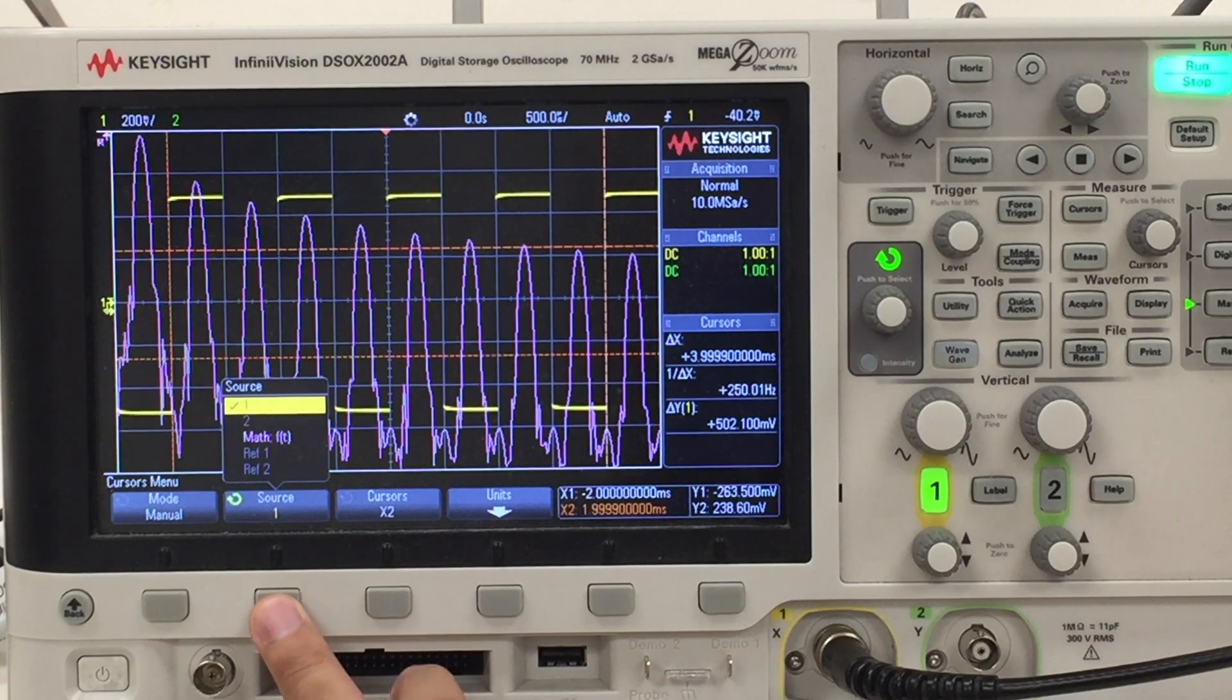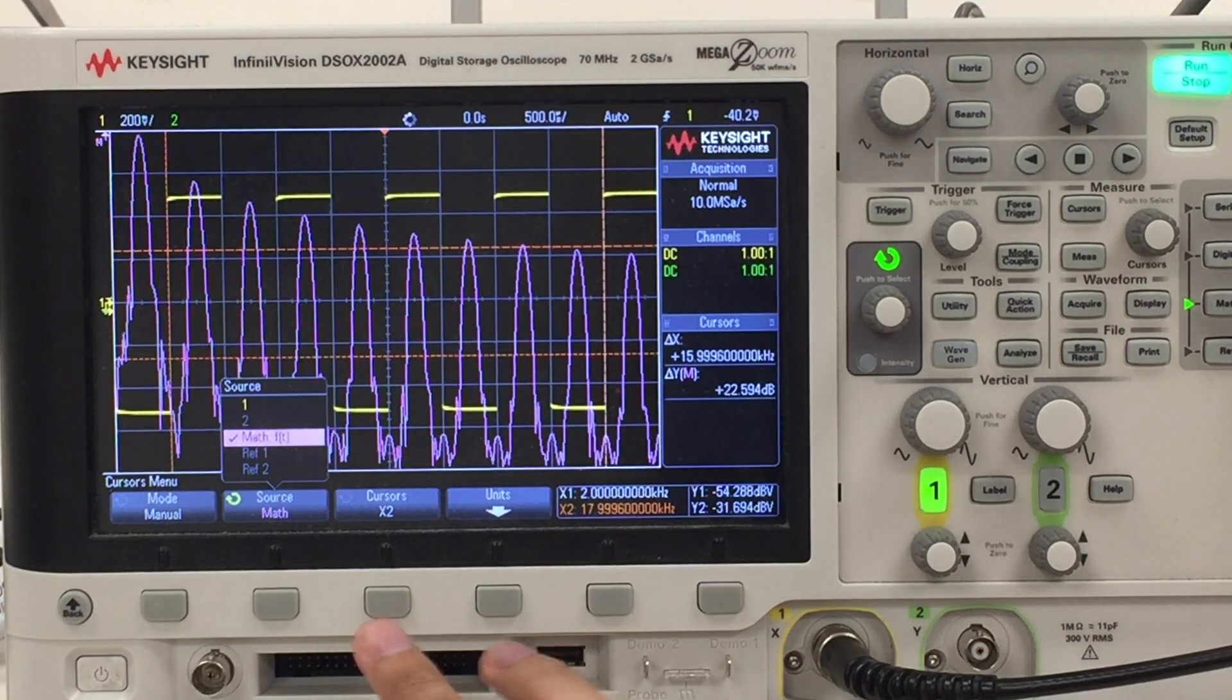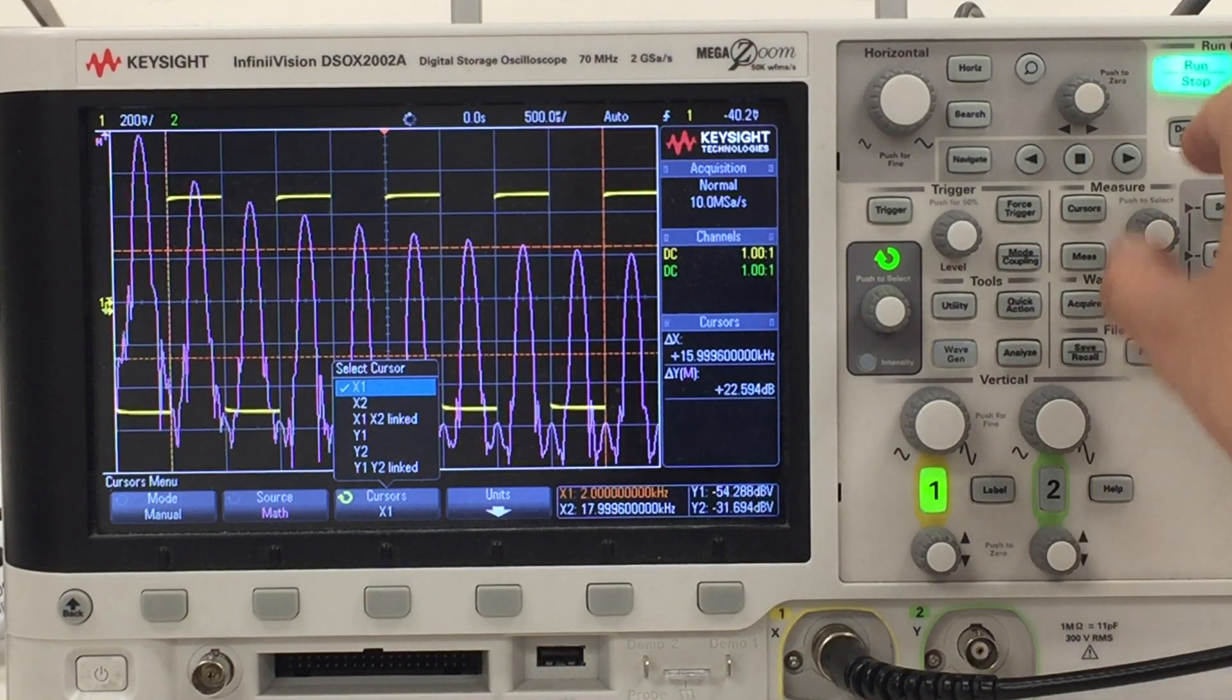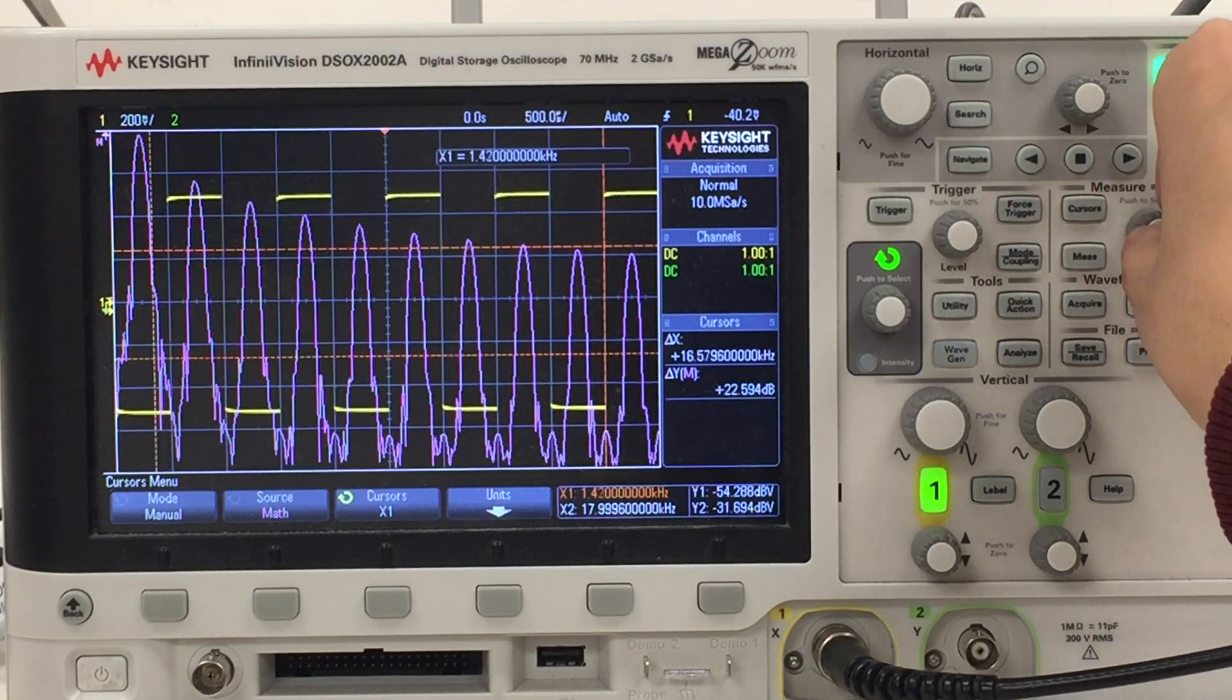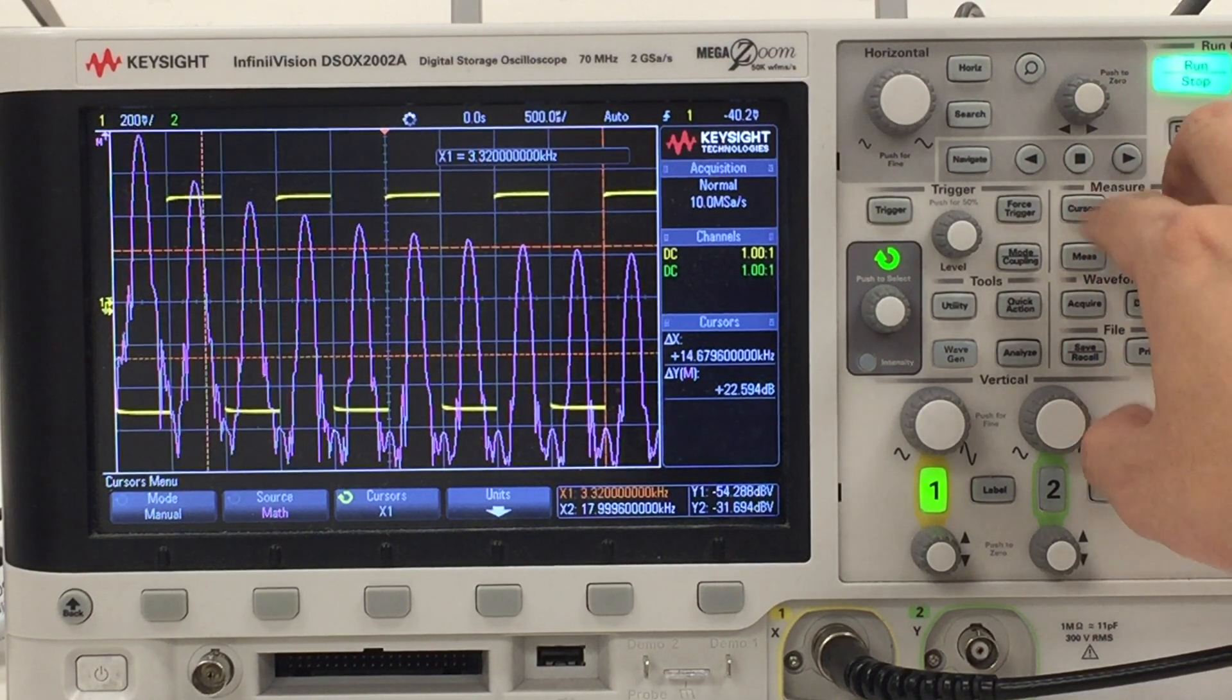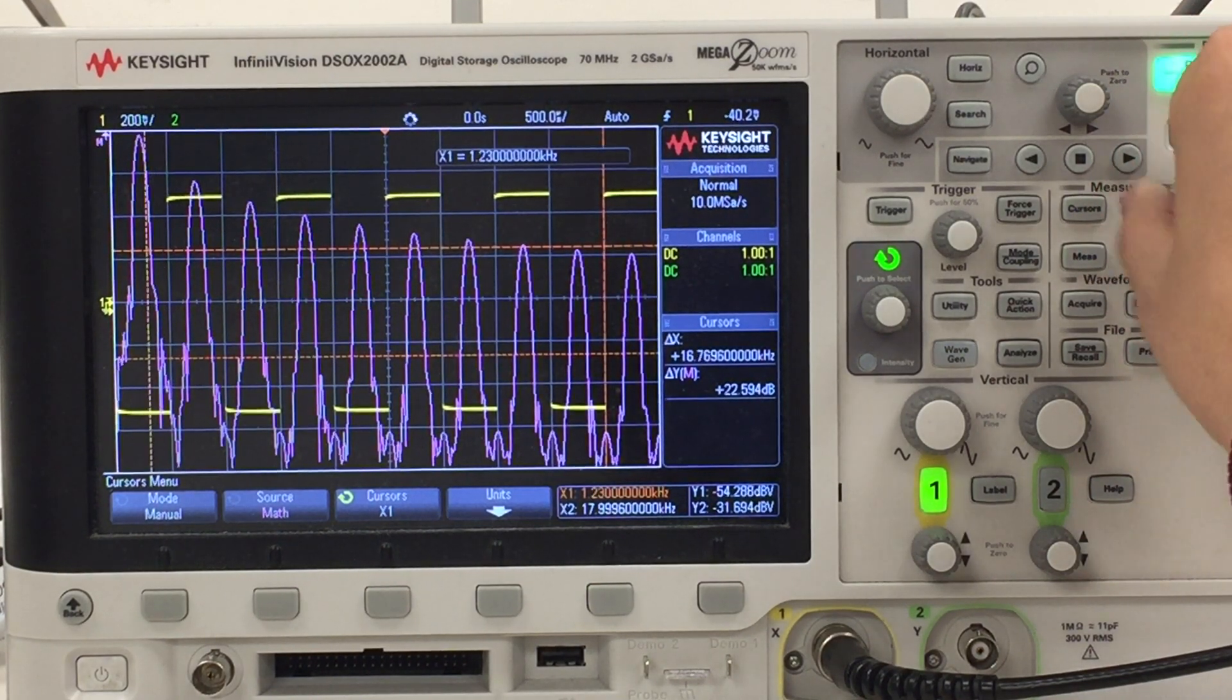The source needs to be on the purple curve, which is the frequency spectrum. Let's do either x1 or x2 and let's move the cursor around. So you can see there's a vertical line moving across the screen as I'm adjusting the cursor. This is actually our cursor. Let's align the cursor with the first peak.